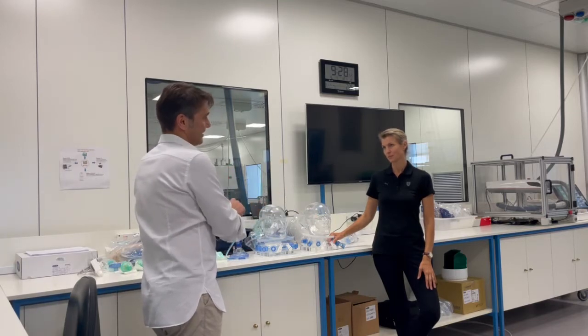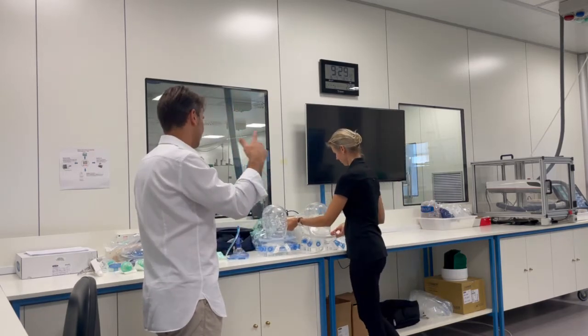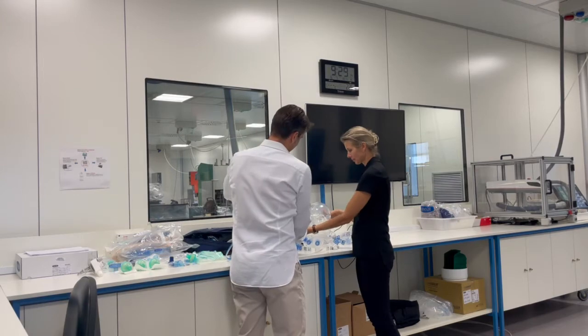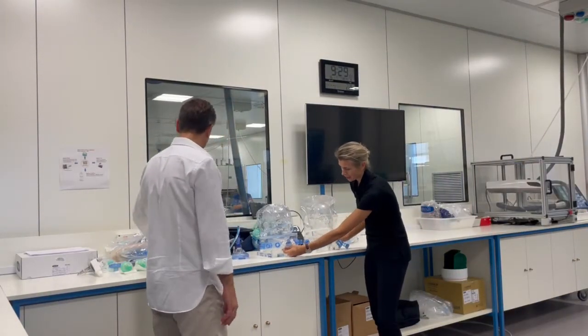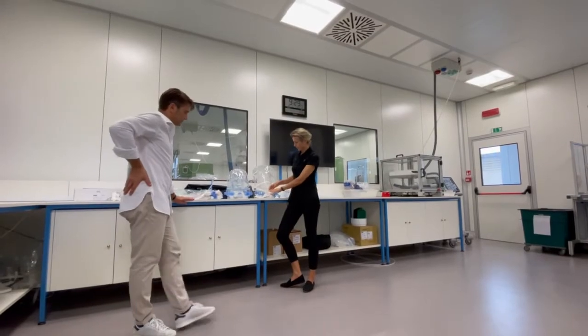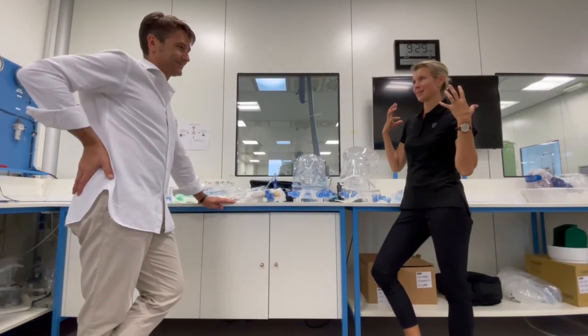So you need to find a way to keep the advantages of the helmet — the softness, no leakage — in a much more rigid device. The neck collar is much bigger and more rigid in a NIV helmet, which is a pressure support ventilation helmet, versus the helmet used for CPAP therapy. The stretchy, thinner neck seal creates a balloon effect, which in the NIV helmet you don't want.